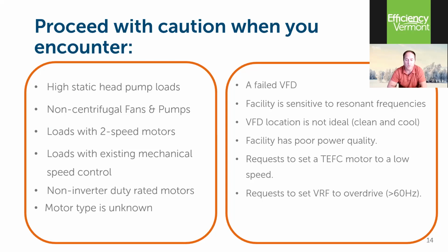But there are quite a few examples out there where there are loads on drives, the drive fails, the motor can still run across the line. It may run in an inefficient state, but it will function and it will operate and it will do its job. If that is the case, then in those scenarios, it's likely that we will be able to support a drive.